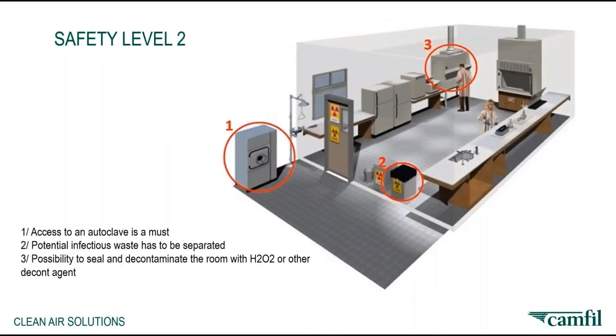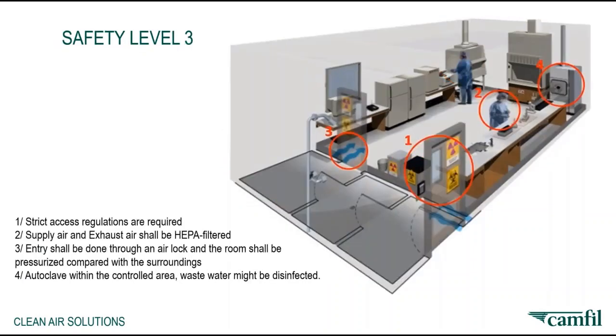The next safety level, number 2, means work in a restricted area. People shall be informed and trained on the risk. Access to an autoclave is a must. Potential infectious waste has to be separated, with the possibility to seal and decontaminate the room using H2O2 or other decontamination agents.